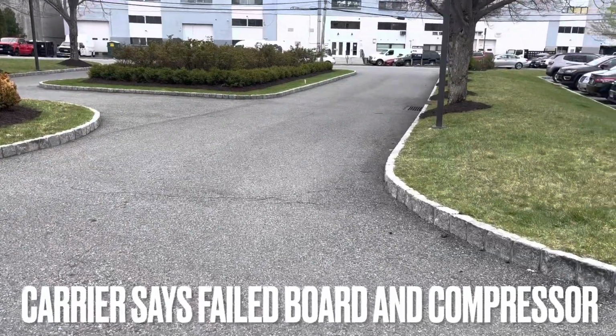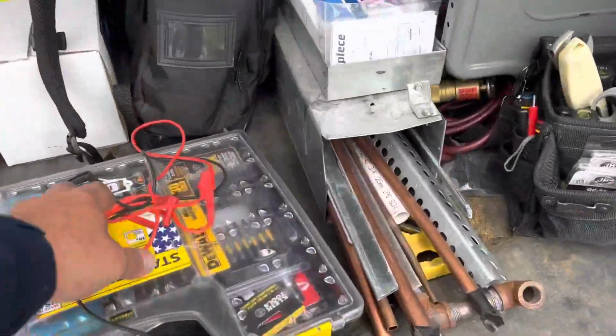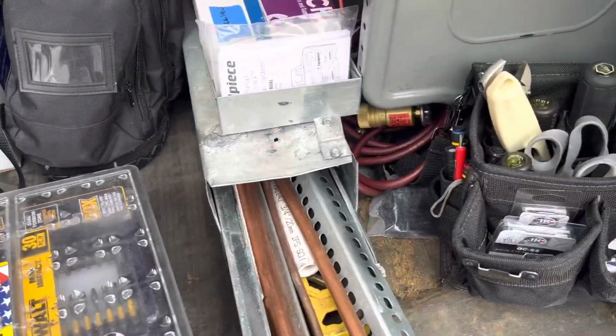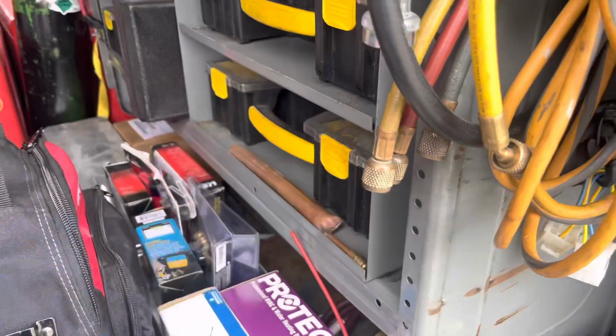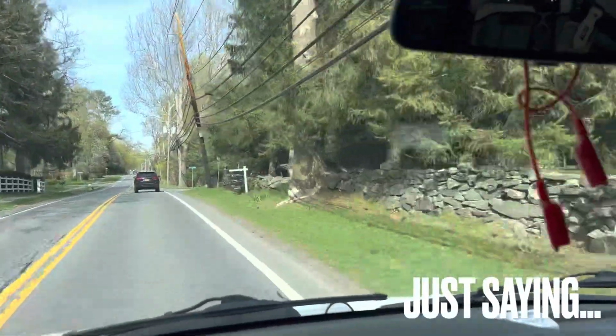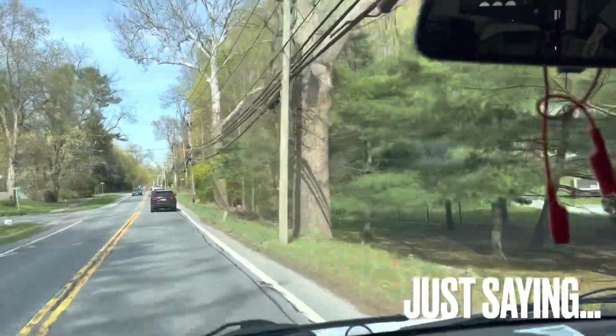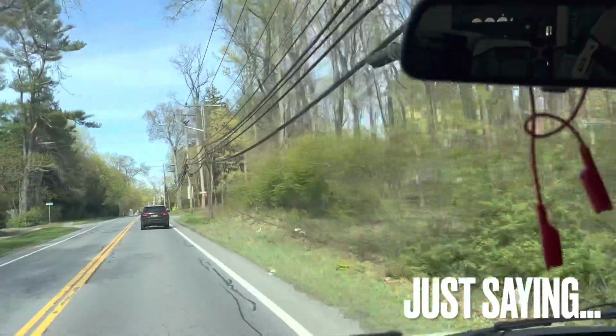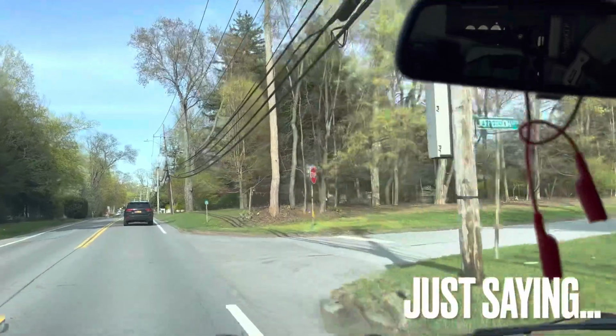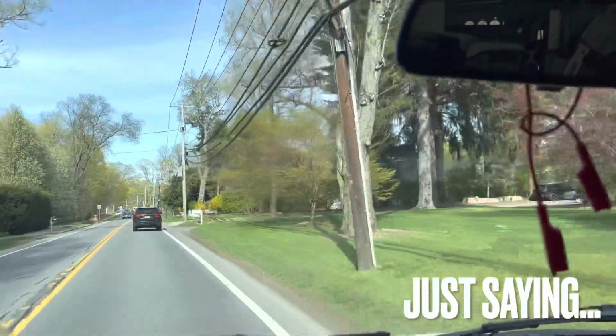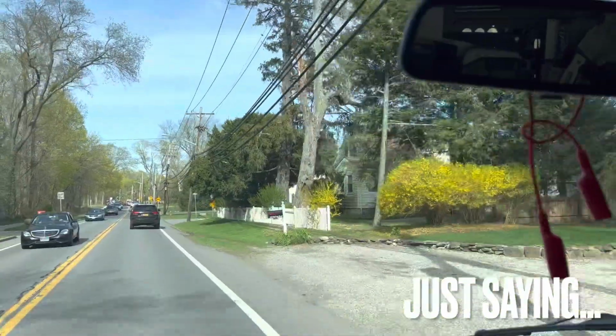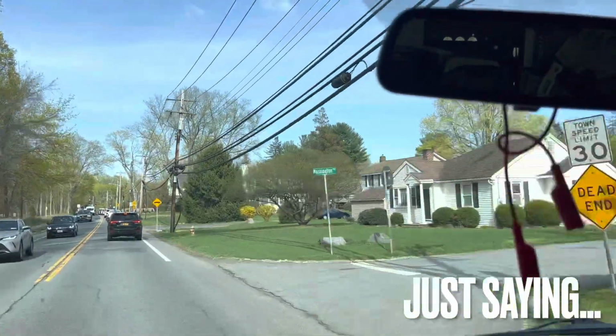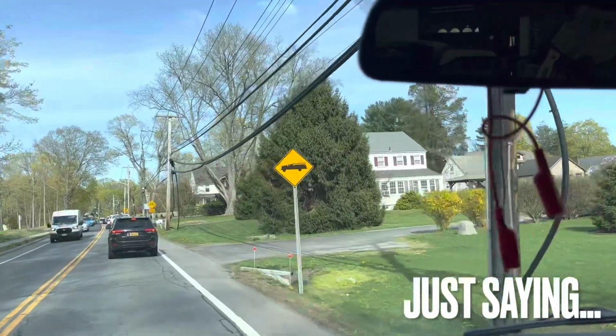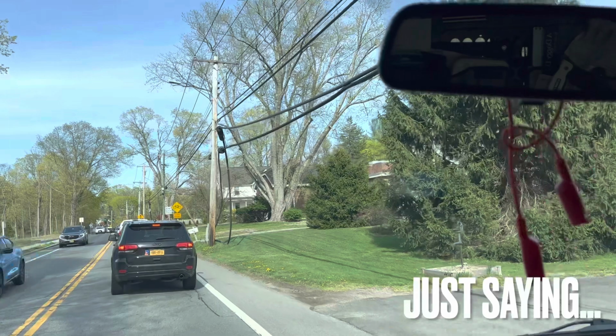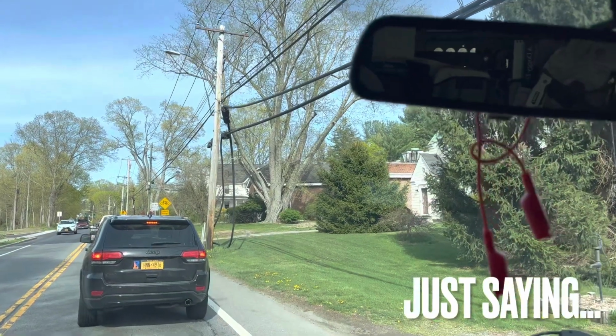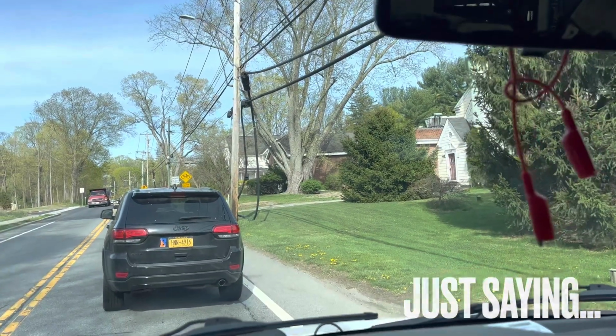I'm going to go on to the next job. Let's see what else is there today. I trust that diagnosis by tech support. Like I said, I would just rather go with the inverter board, and tell the customer that tech support recommended the compressor and the board. But I don't know. The compressor checked out good to me, based on the values anyway, all being, I think, 0.2 or 0.3, whatever they were. Who knows? All right, I'm going to the next job.